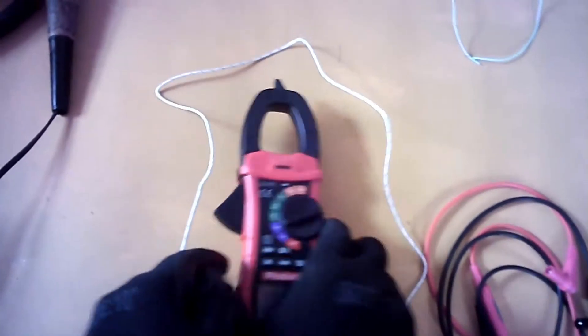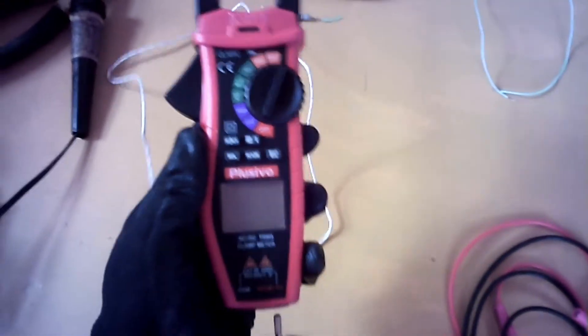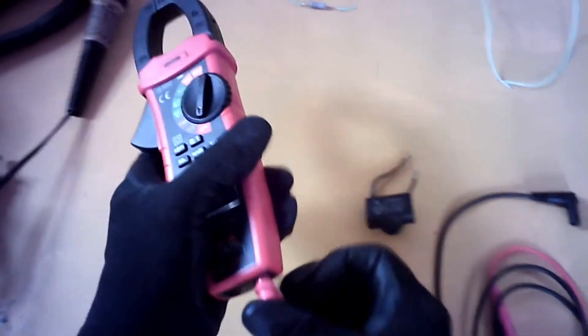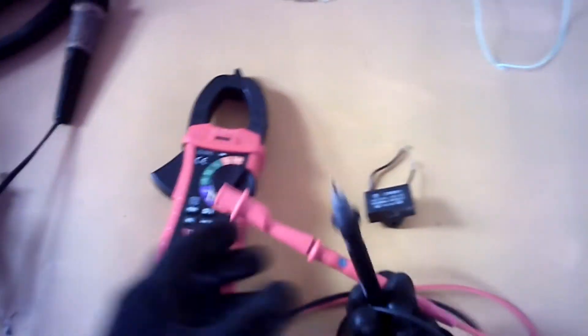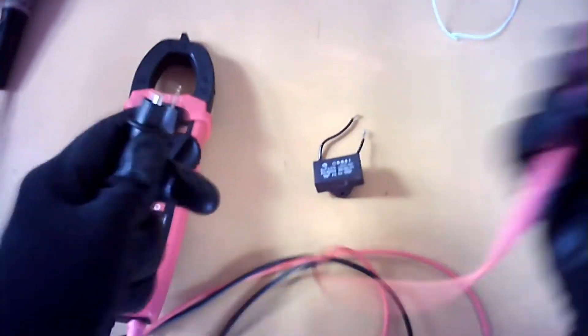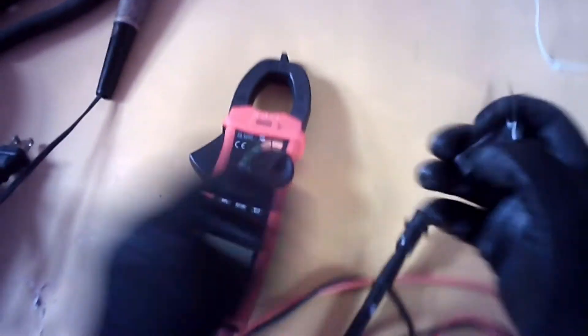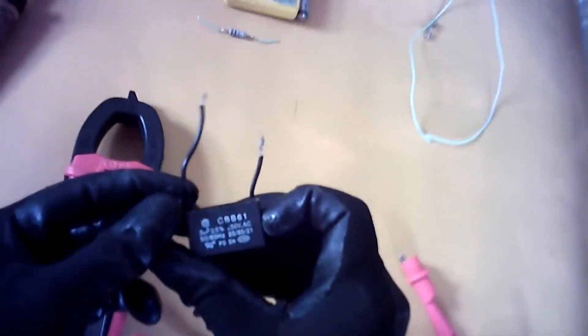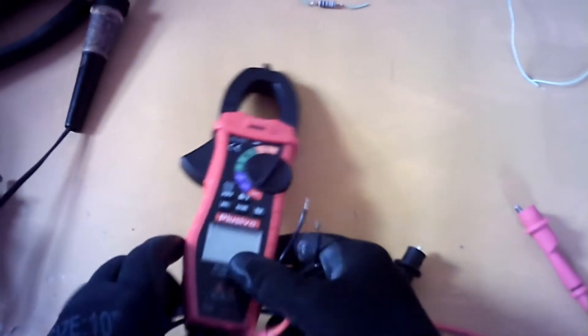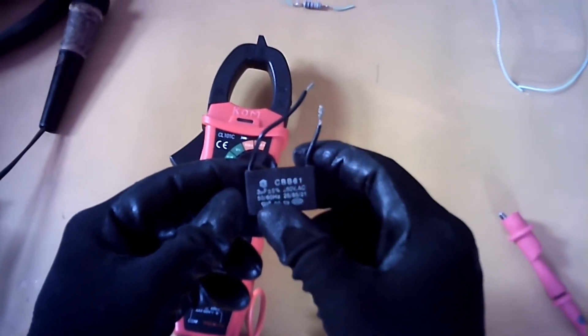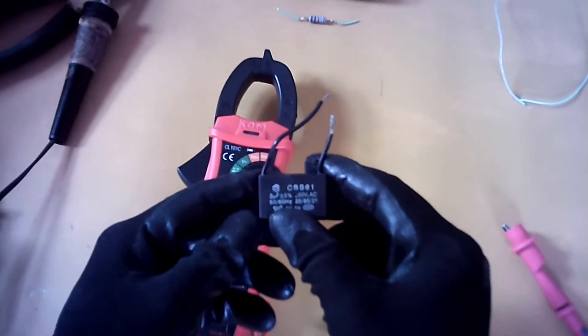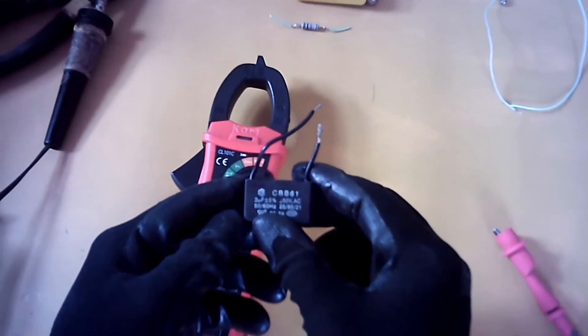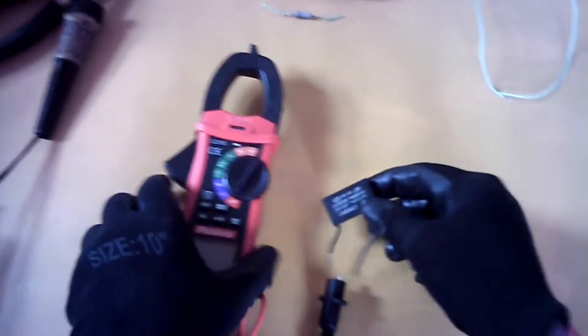Now I am going to do a capacitor check. I'll use my test probes. I am going to use my alligator leads. And this capacitor is rated at 3 microfarads plus or minus 5%, so I should get at least 3.3 or about 2.95 less for it to be good. So let's check that.